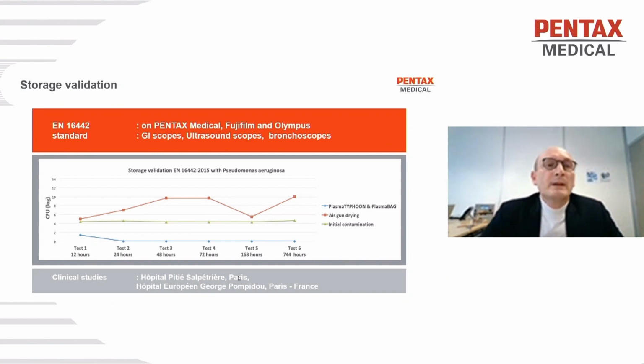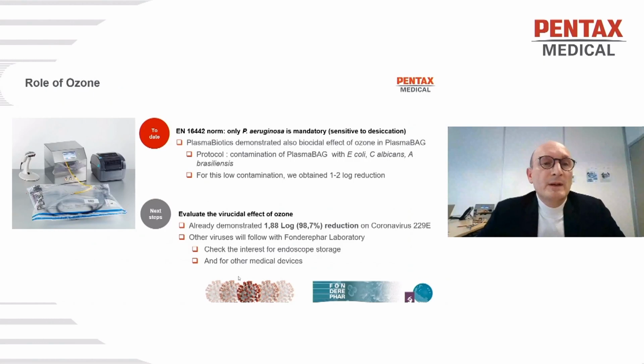So the role of the ozone. For the European norm, only Pseudomonas aeruginosa is mandatory. We know that this pathogen is sensitive essentially to desiccation. So if we dry the channels correctly, Pseudomonas aeruginosa will disappear. So Plasma Biotics went further and also demonstrated a biocidal effect of the ozone inside the plasma bag.